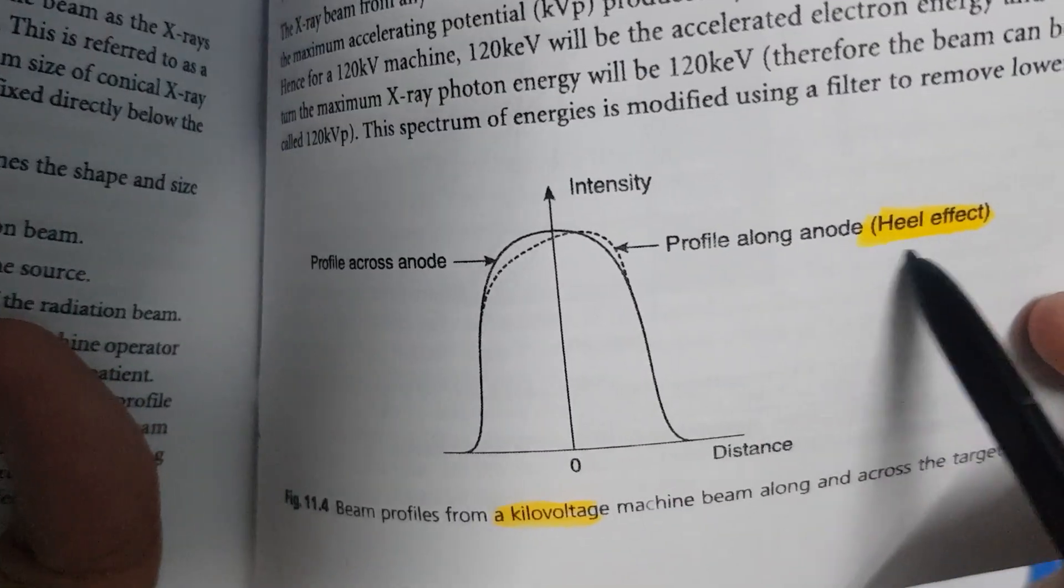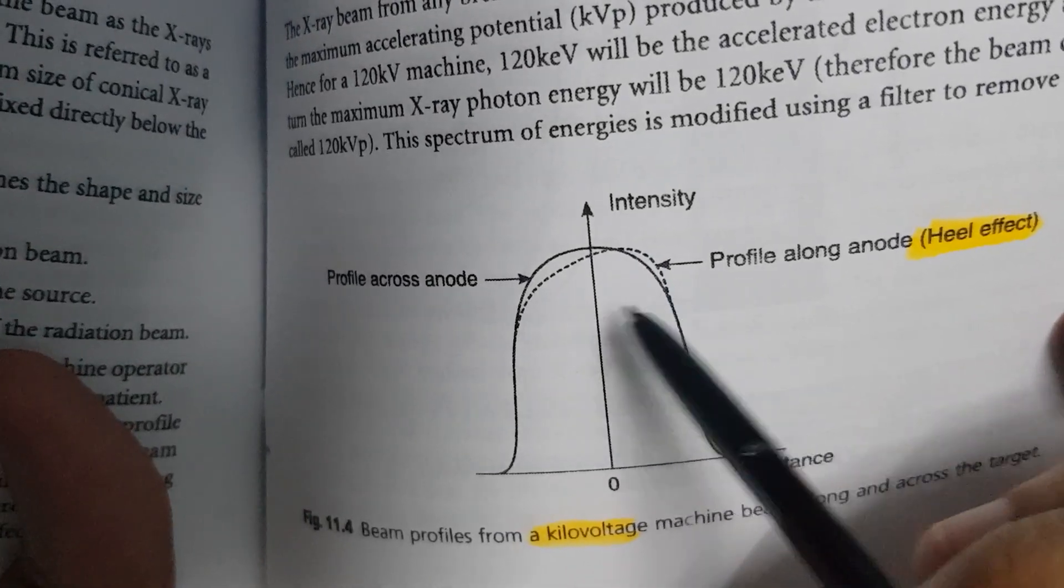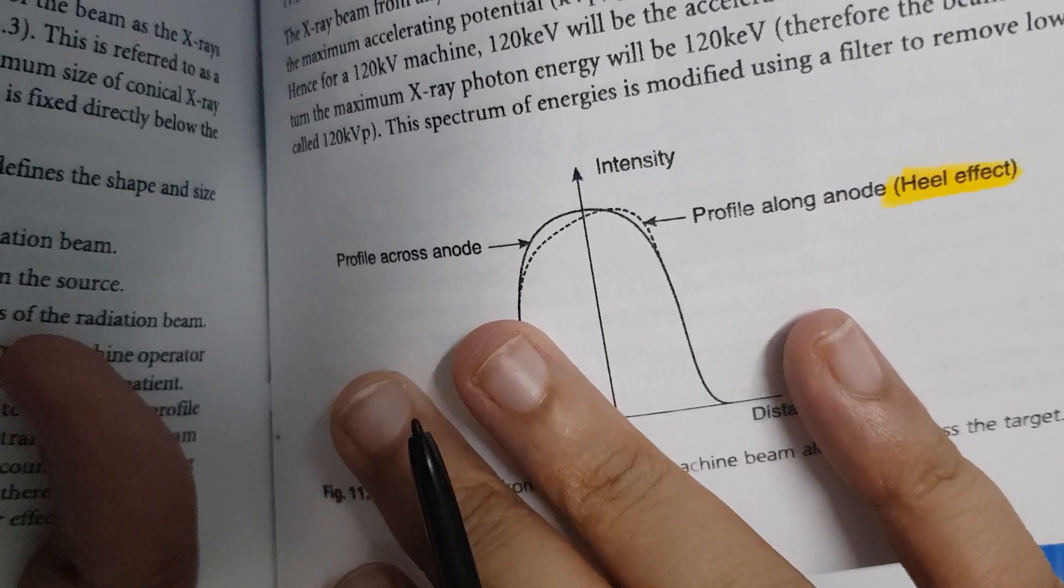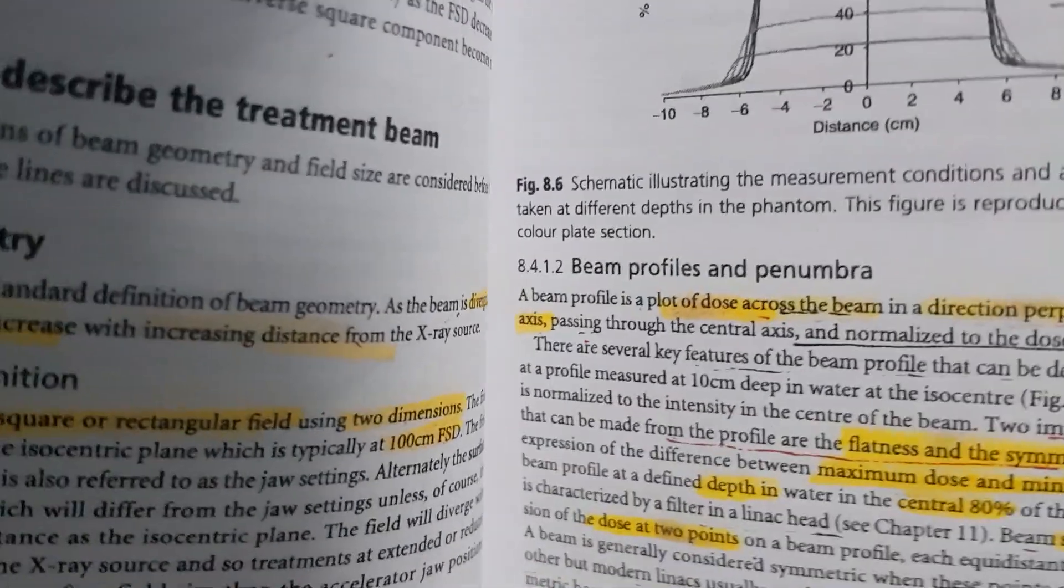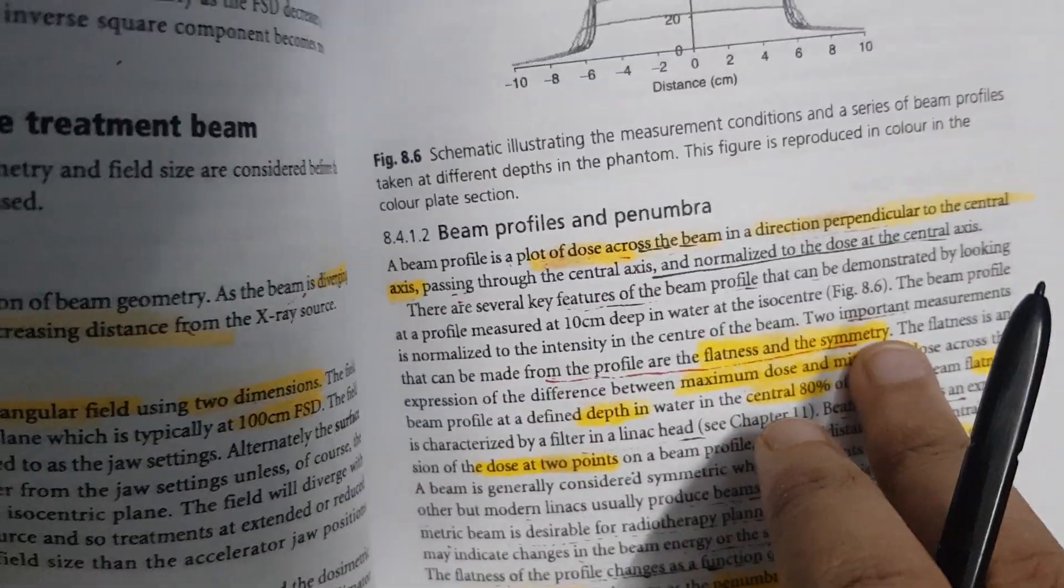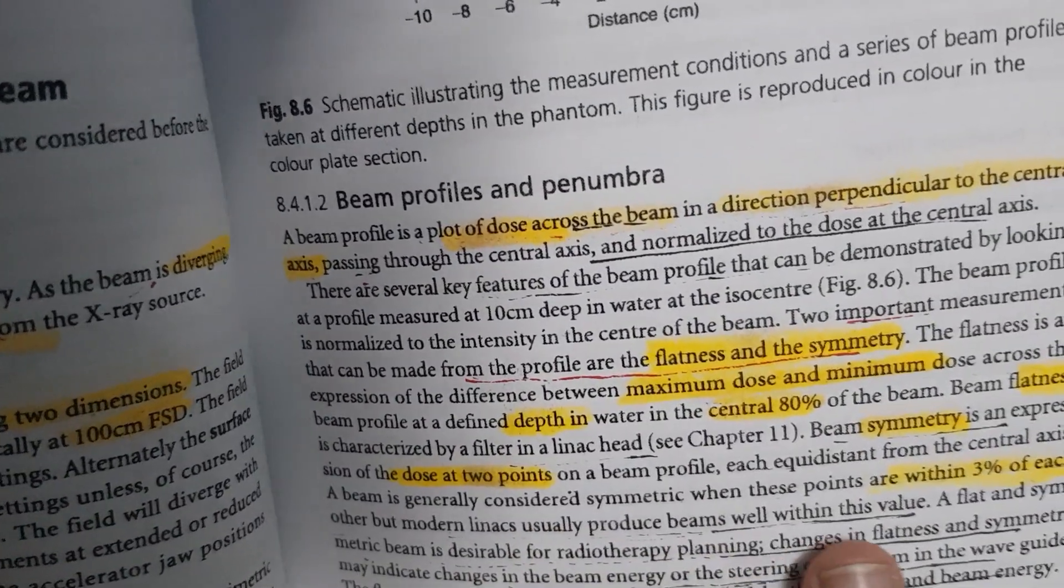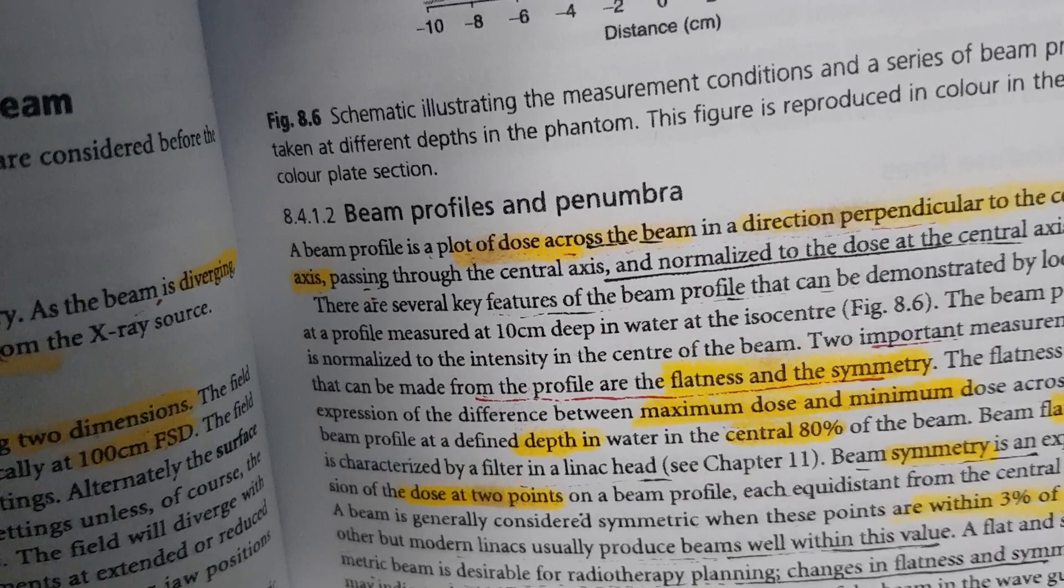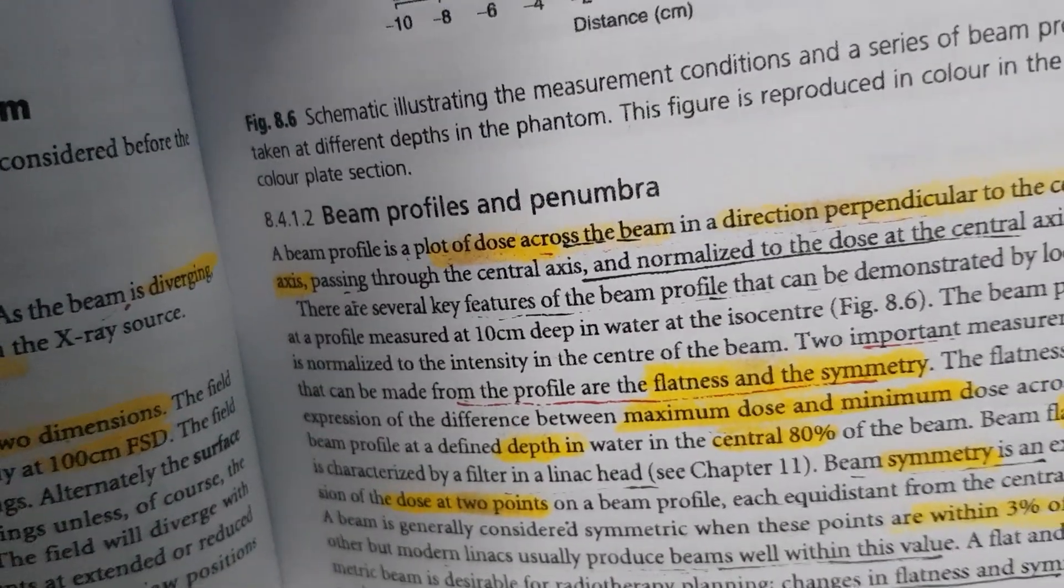If you consider this kilovoltage beam profile, then we can see that there is something called as heel effect where the symmetry is not proper. So you can see the flatness is also lost, the symmetry is also lost. That's the difference. That's why we need proper flatness and symmetry for us to know how well these are functioning for the desirable radiotherapy planning.